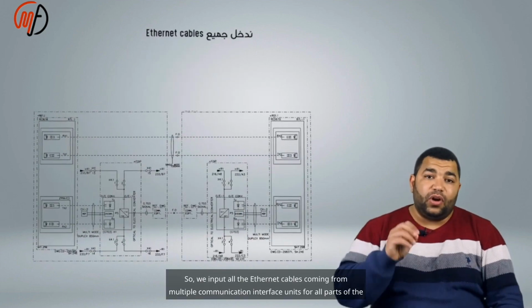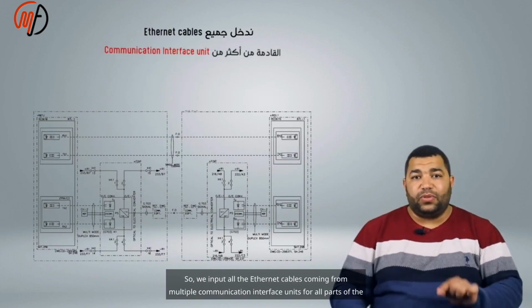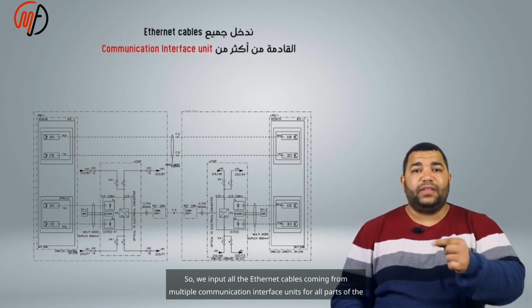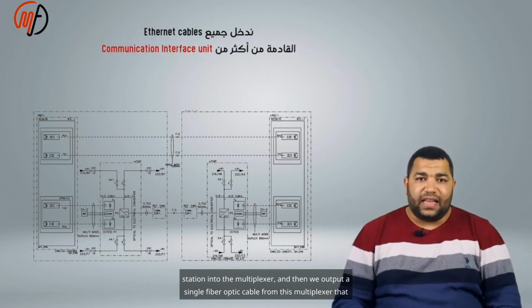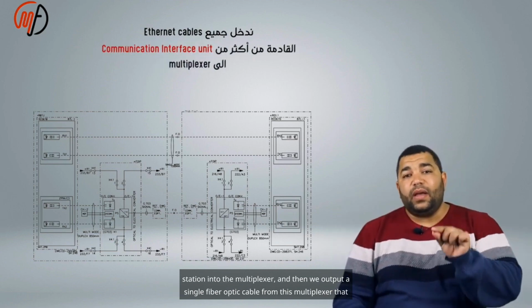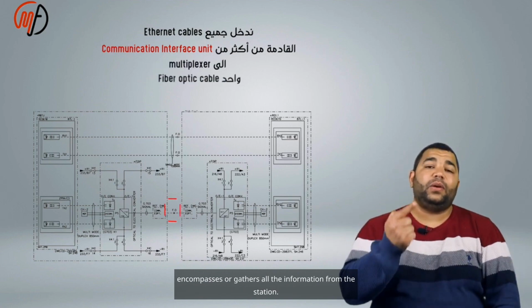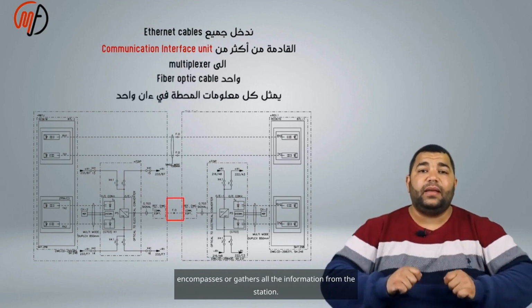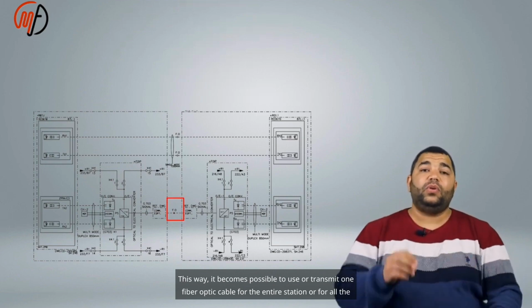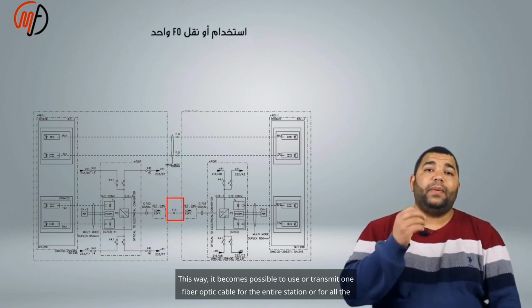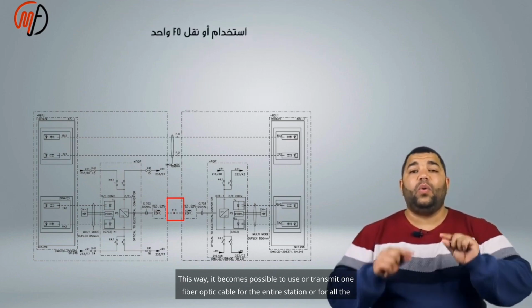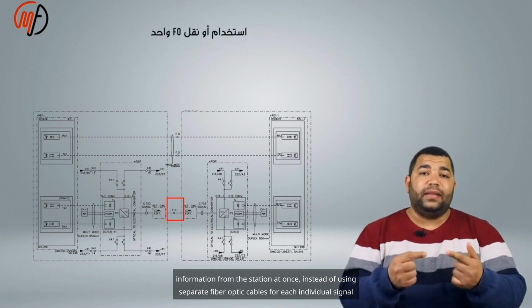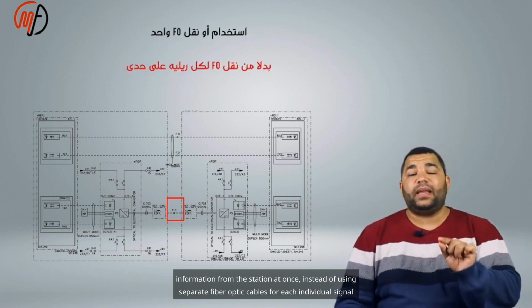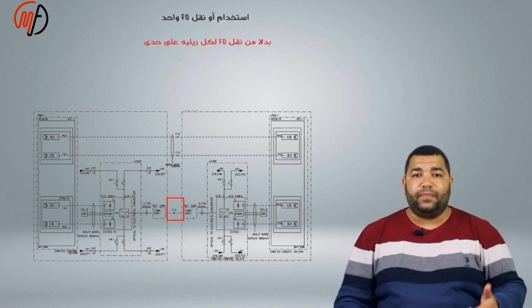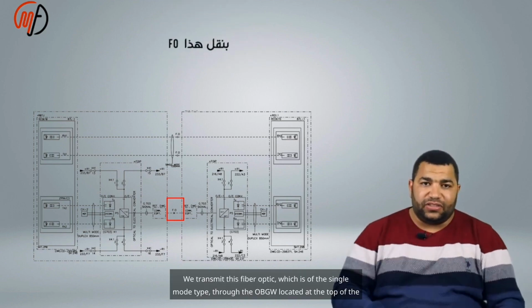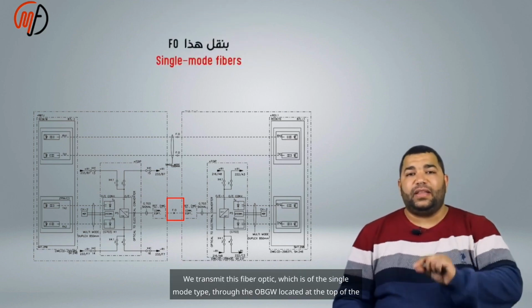So, we input all the Ethernet cables coming from multiple communication interface units for all parts of the station into the multiplexer, and then we output a single fiber optic cable from this multiplexer that encompasses or gathers all the information from the station. This way, it becomes possible to transmit one fiber optic cable for the entire station, or for all the information from the station at once, instead of using separate fiber optic cables for each individual signal.